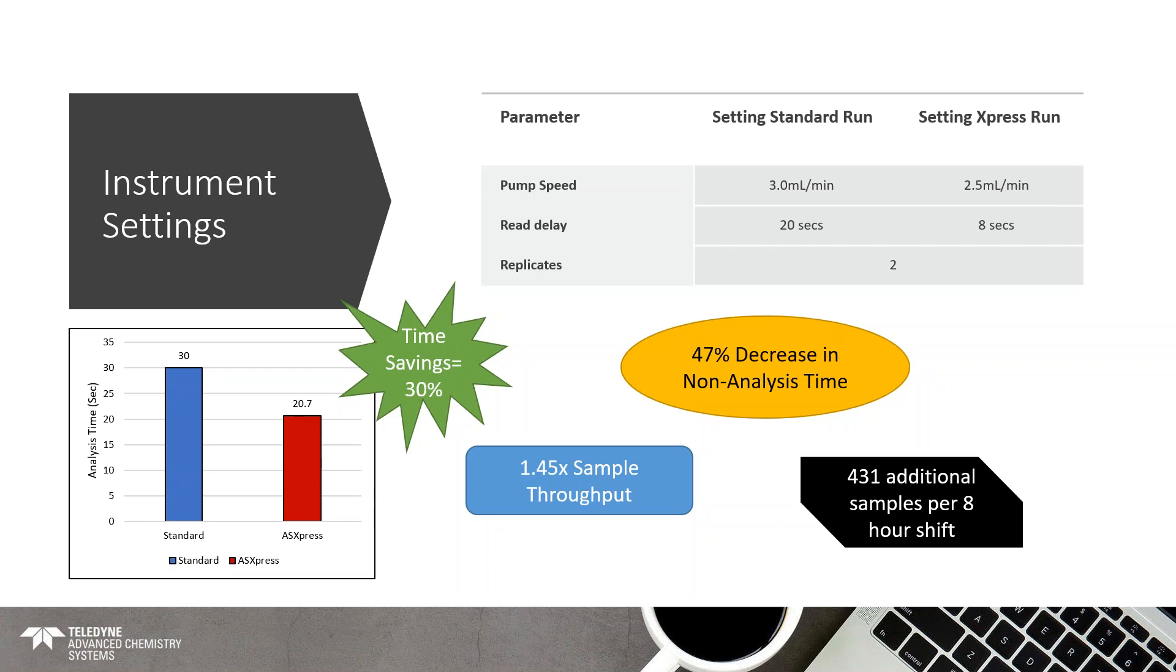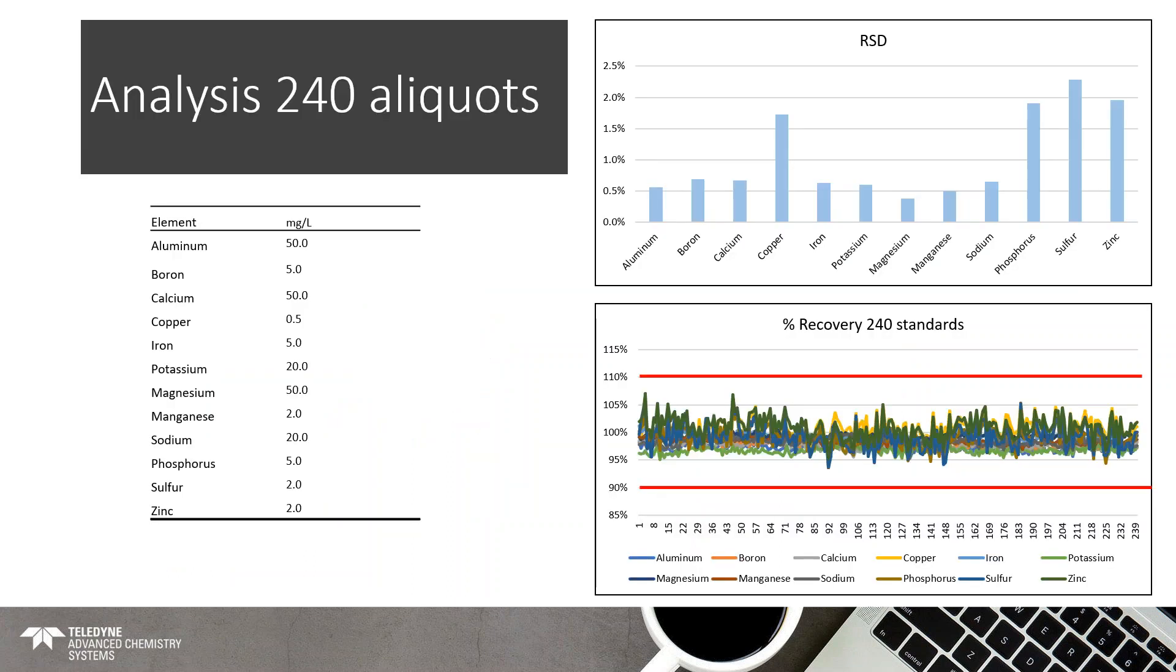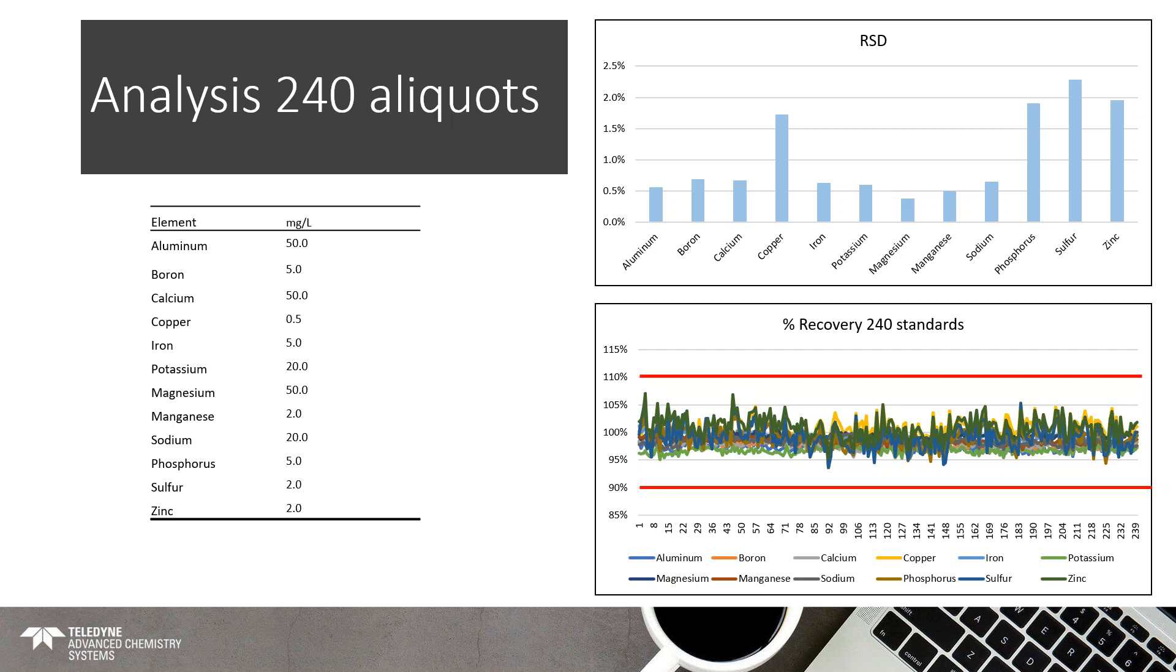So, with that in mind, let's look at the data. Because, of course, the most critical thing is always maintaining your data quality. So, what we did here is we ran 240 aliquots of a known sample. Essentially, we poured up just the whole autosampler full of them. We ran it over and over and over again to get percent recoveries and to look at RSD. So, our average RSD across the board, you can see in the top right, we're able to get under 2% for everything except sulfur. And that's going to have – so, good RSD, especially for only having two replicates. And then our percent recovery is in the bottom. The big red bars there are the 10% mark. Everything falls easily within the 10%. Almost all of it falls within 5% recovery. So, we're getting really good recoveries, and you can see even across that whole time, very little to no instrument drift can be seen. So, good recovery. And what that really means is having this extra speed, you can get more samples per day, but also more samples per calibration curve. Because we want to help you be able to run for as long as possible before you have to recalibrate your instrument.